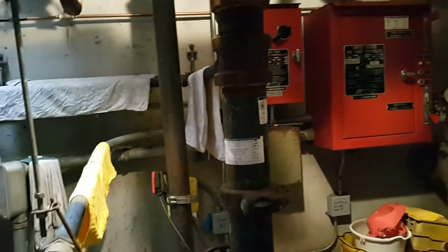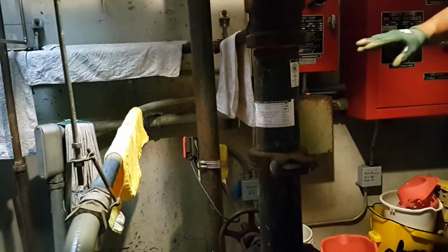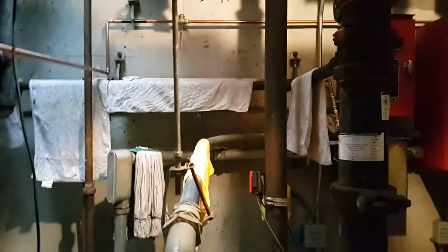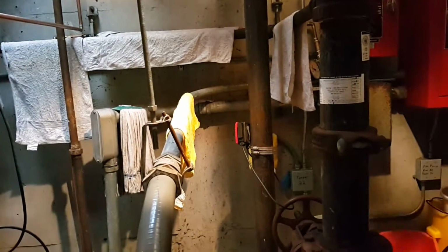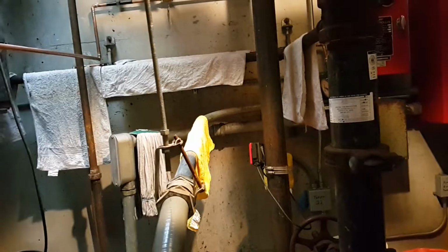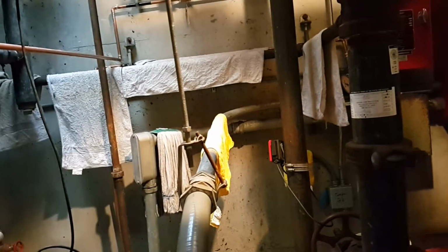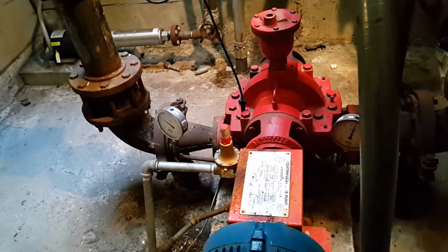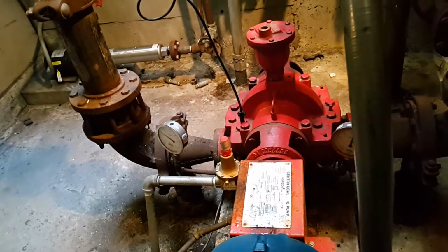Yeah, but that one you don't need any water dripping, you just need to make sure that it's on and make sure you have adequate pressure all the way to the top. So we can deadhead like that and it won't overheat? The jockey pump, yeah, that's fine. And this one, the relief valve, that's enough flow that it won't overheat either. Exactly. Cool.